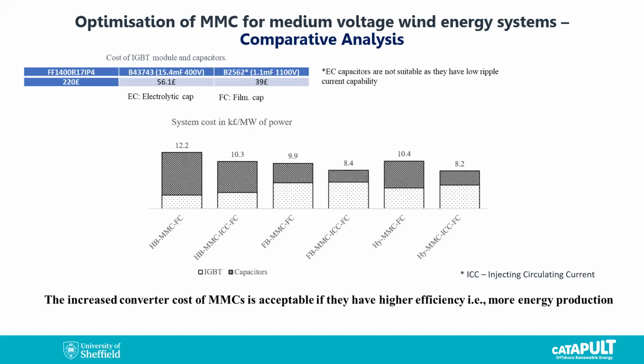So this shows different designs, starting from the left with the half bridge. Then if you can click once more. Here is the optimum solution for the full bridge. What we are looking at here is the cost of the IGBTs and capacitors. The blackish area is the capacitors, and the IGBTs are the white areas with the dotted signs. We can see from the left side that the half bridge needs lots of capacitance, so the cost is high, and in this optimum solution we are squeezing the capacitance, and so the cost as well. But we can notice that we then need more IGBTs because it's a full bridge, so we have more devices. Then we said, okay, maybe we can go with a hybrid solution. If you click once more, that would be the last, or at least at the moment what we have when it comes to the hybrid solution.